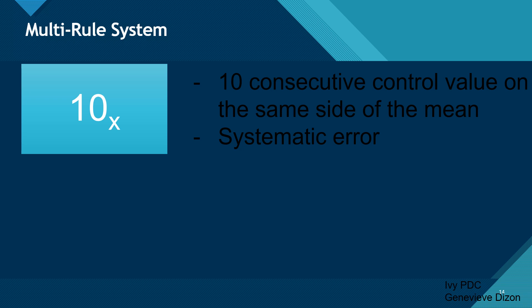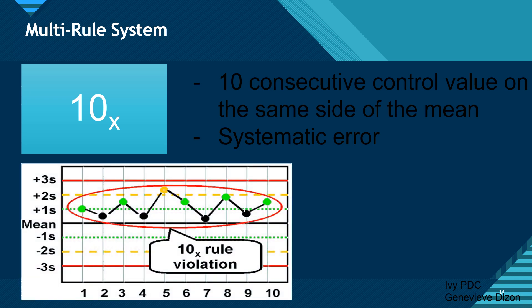The last rule is the 10-X rule. These are 10 consecutive control values on the same side of the mean, and this is also a systematic error. It doesn't matter if they are at the 1, 2, or 3 standard deviation level — as long as there are 10 consecutive values on one side of the mean, it can be on the positive or negative side. This detects bias, which is an accuracy problem. When we have a result like this, we reject the specimens that have been tested.